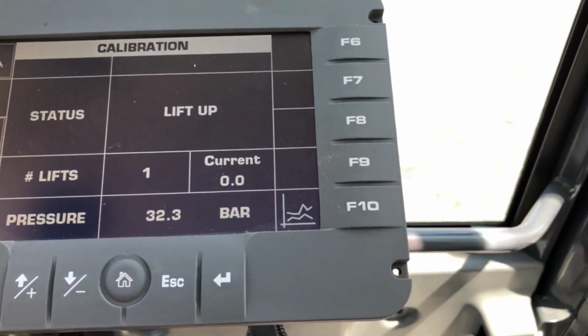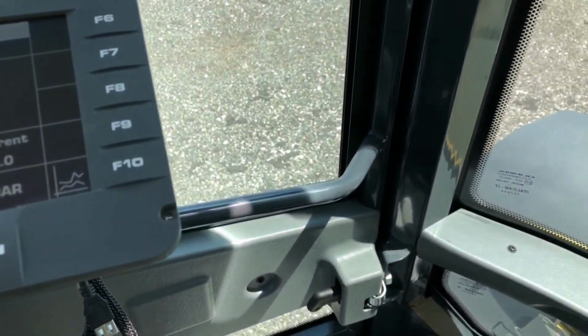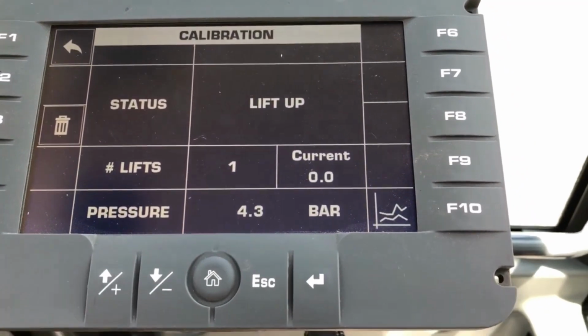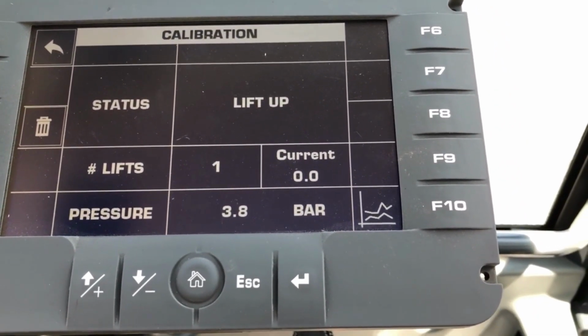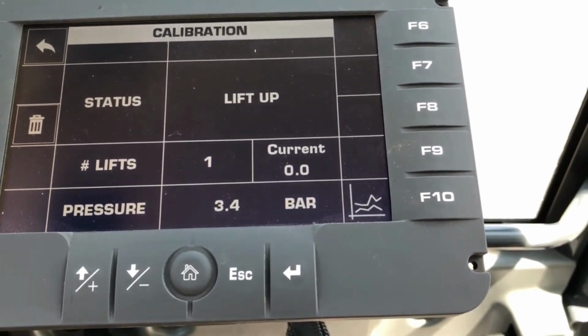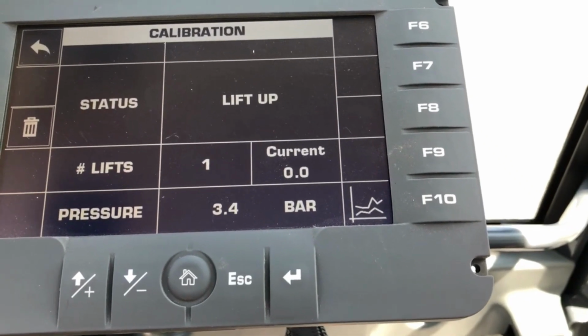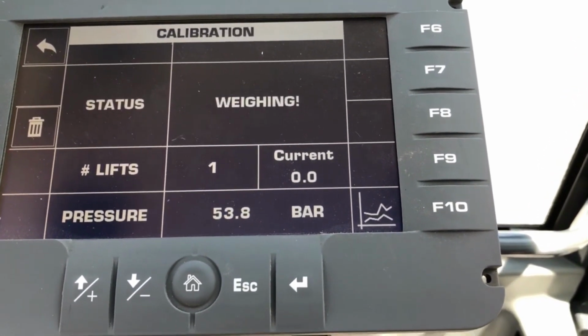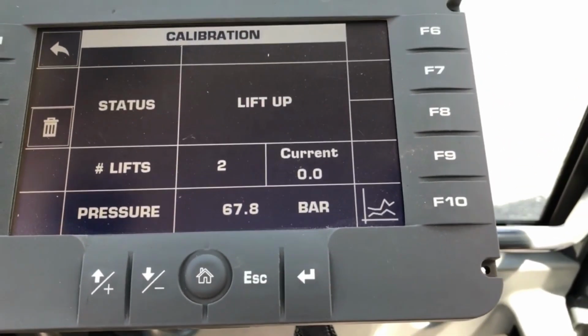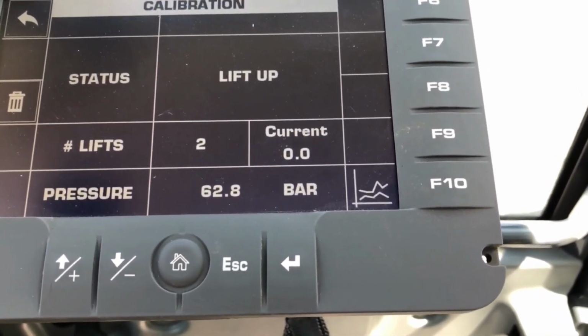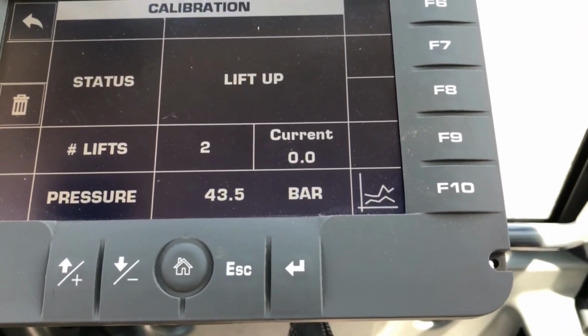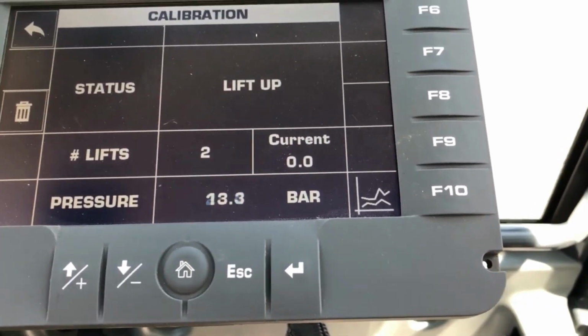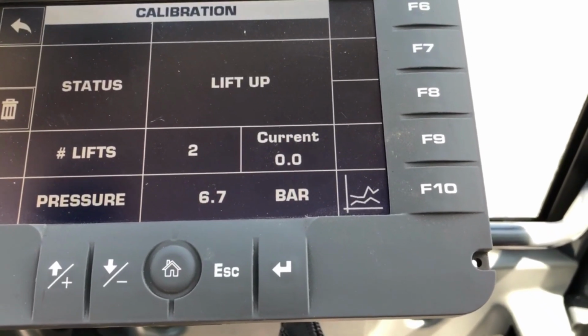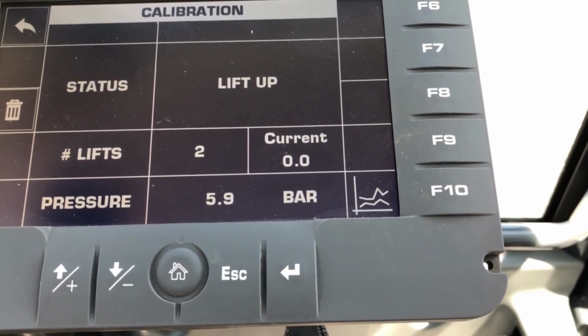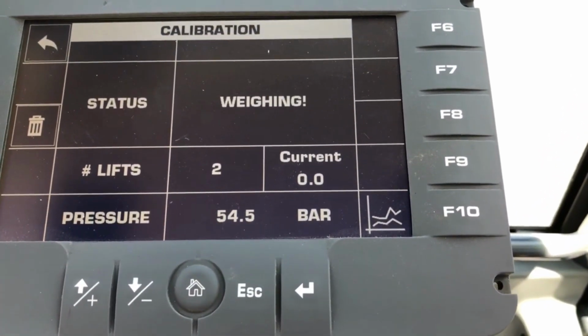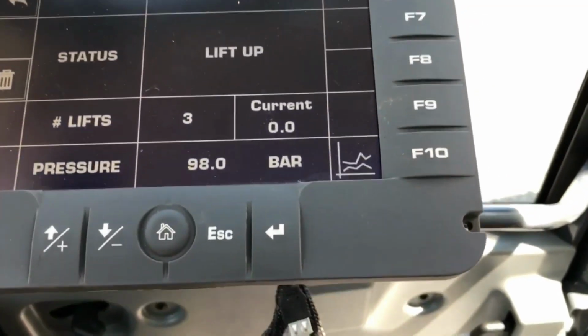We recommend doing multiple lifts at multiple speeds. So I'm going to continue coming down about 100 RPM. So it's about 2100. I'm going to go to 2000 and work my way down. So I'm going to do another lift to 2000. And that one is completed. Go all the way back down. Now I will go to 1900 and this will be the last one I show you. This one. So there's weighing point or calibration point 3.